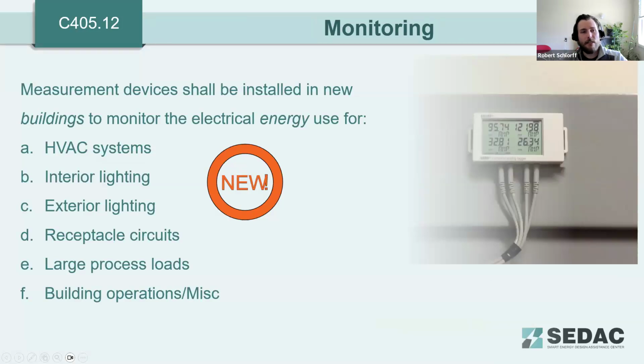So, energy monitoring, C405.12. This is another new requirement in the 2021 code. Measurement devices shall be installed in new buildings to monitor the electrical energy for the following systems: HVAC systems, interior lighting systems, exterior lighting, receptacle circuits, large process loads, and building operations and maintenance. This new requirement only applies to buildings that are 25,000 square feet or larger. And this is another alignment between the IECC and ASHRAE 90.1.